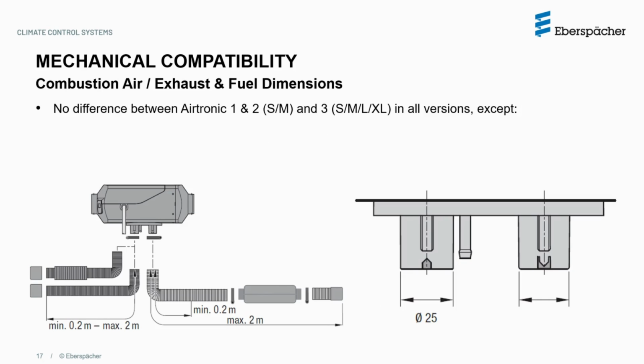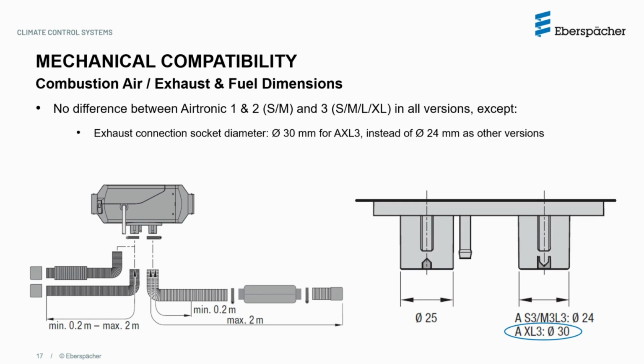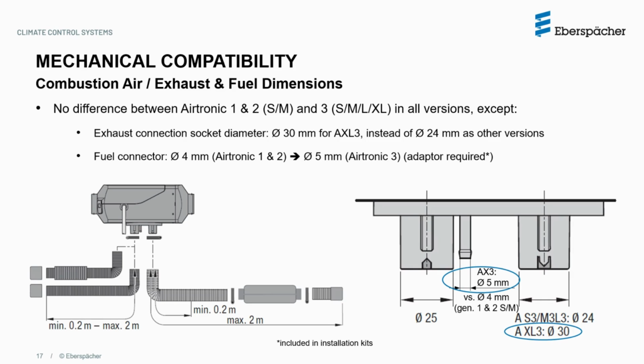If we look at the combustion air and exhaust, there isn't generally any change in diameters and permitted minimum and maximum lengths compared to the previous small and medium-sized heaters, and these rules apply to all sizes of the third generation. The exception is an exhaust connection socket diameter of 30 mm in the extra large size compared to 24 mm in older versions. Another difference in the third generation is a fuel connector diameter of 5 mm for all sizes compared to 4 mm in previous generations of small and medium-sized heaters. This diameter requires an adapter that is included in the installation kits.